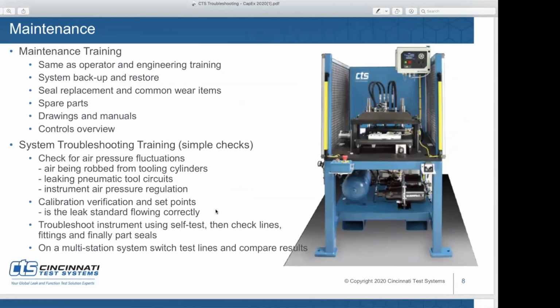And the keys to the maintenance department for correct operation. When you start working with an instrument, my suggestion is to always back the system up. That way, if you make some changes that weren't correct, you can always go back to the way it started. Especially nowadays, with just popping a memory stick in there and doing a quick backup, it's no time and a no brainer, right? Yep, absolutely. All our instruments have a USB interface for backup and restore. Man, if only the I-21s had that. Well, that's why we help our customers replace those as they wear them out. Those were a workhorse. We still see them in operation even from 25 years ago.